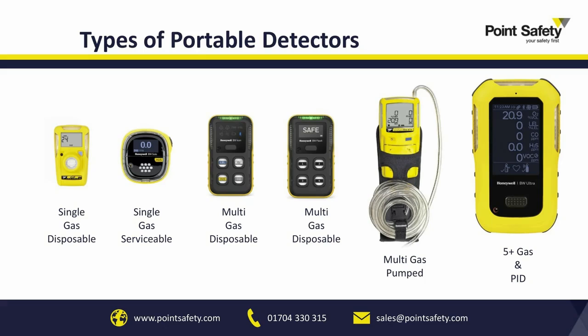You will then move on from the single gas, because single gas is generally only available in 3 or 4 different sensor configurations. We'll be looking at H2S, CO, oxygen, SO2 primarily, and then we'll move on to single gas serviceable instruments, like the second one here on the screen. These are a little bit more in depth. They generally will have an instant reading on the screen. They'll be available in a myriad of toxic gases, and some manufacturers do flammable and PID in single gas as well, for VOCs and volatile organics. A vast range is available for most applications.